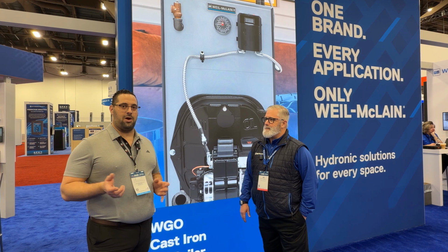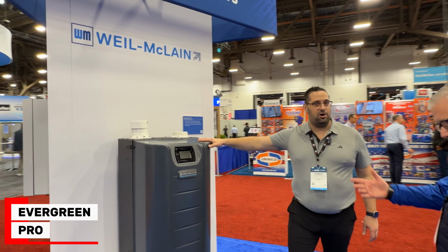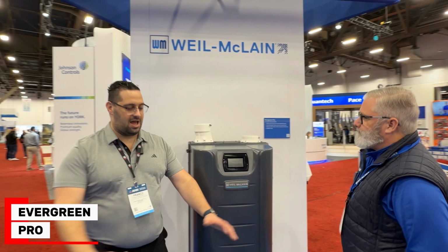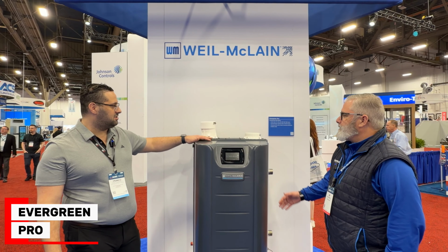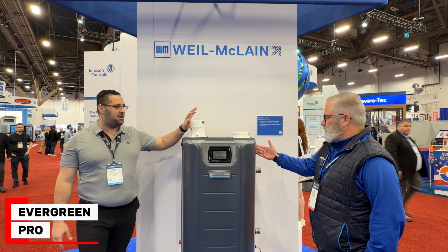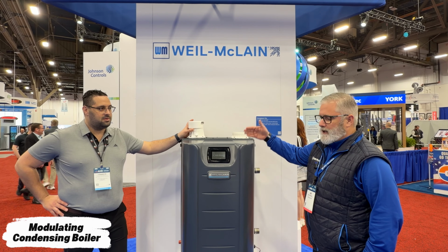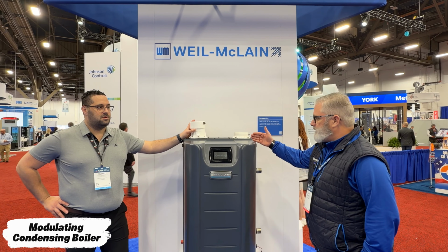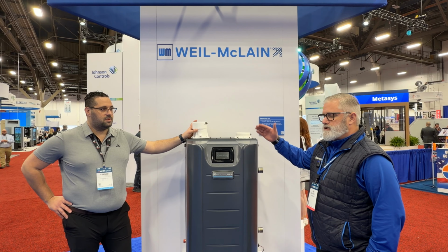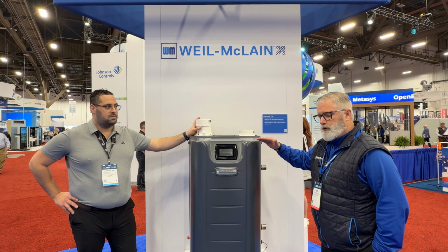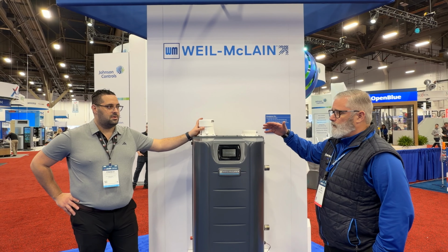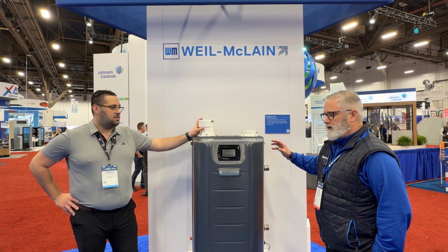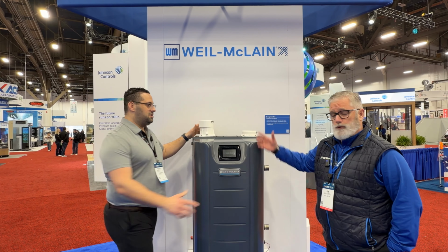So very cool process. Let's take a look at a couple of the options that we have with Weil-McLain. How is this different from your standard cast iron boiler single stage? This is a modulating boiler, right? Correct. It's a stainless steel vertical fire tube heat exchanger. It modulates so it saves the user fuel, and it's high efficiency so that you can get the best out of both. So this one's pretty big.